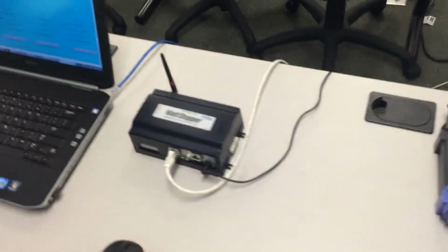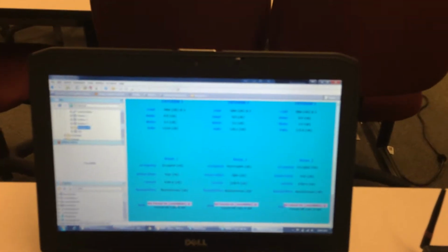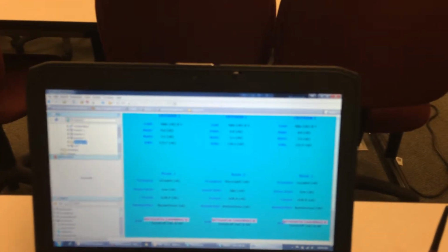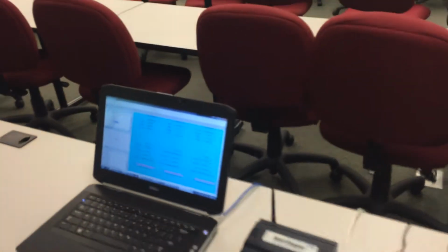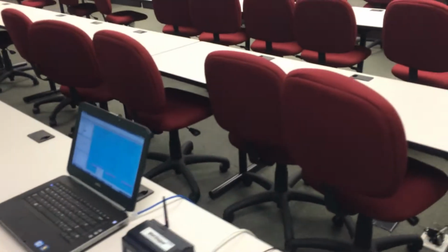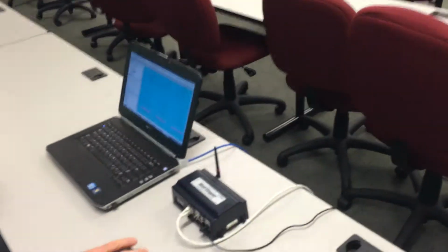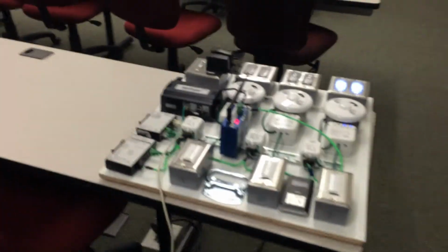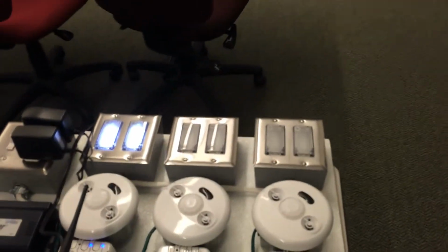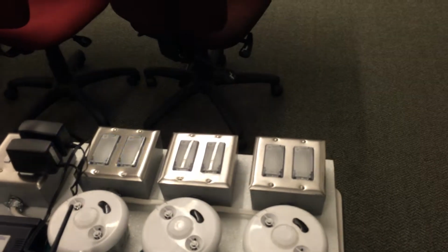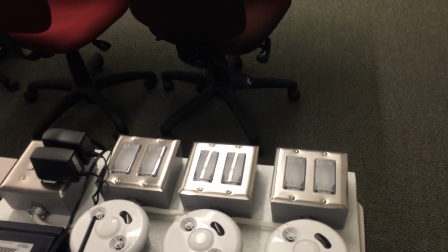Here's our segment manager, and he's built just a PX page in the Niagara framework that is our segment manager. He's just built a simple user interface. And Elliot, what I'd like for you to do is just start off by demonstrating how, just through a normal browser, we can control loads in the DLM rooms. So he's just going to communicate to the segment manager across Ethernet, through the Ethernet switch, the MSTP bridge, into the DLM rooms, and he's activating loads on and off through a browser that can be located anywhere.